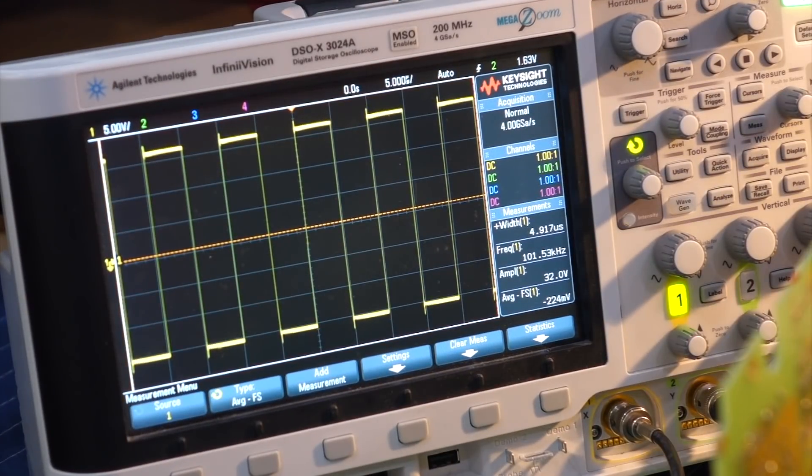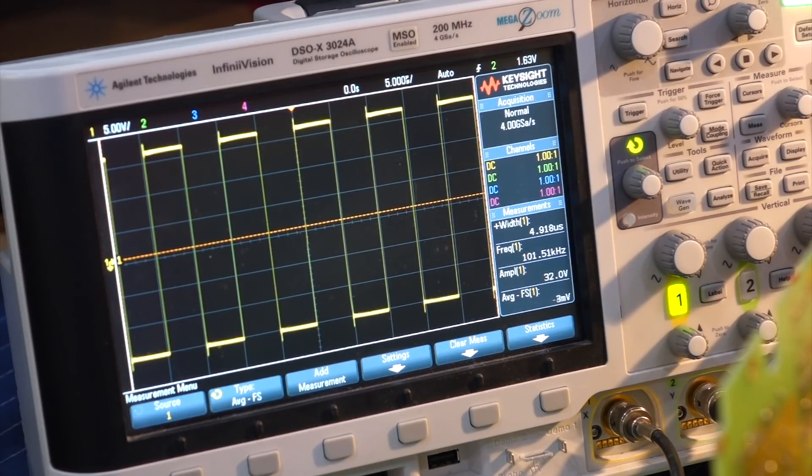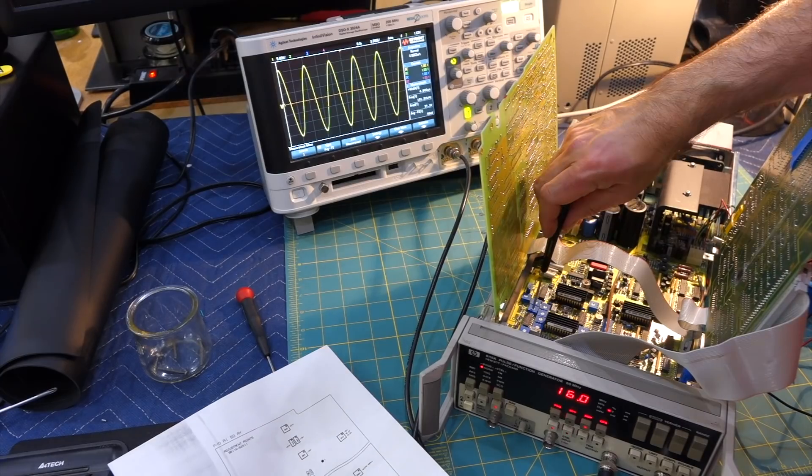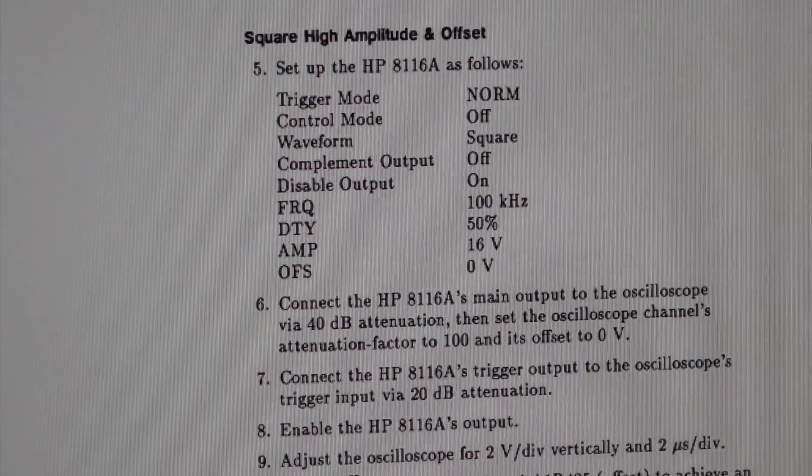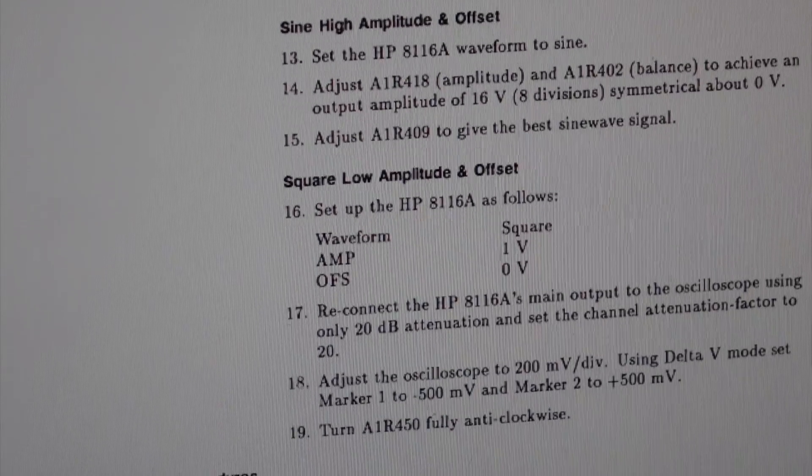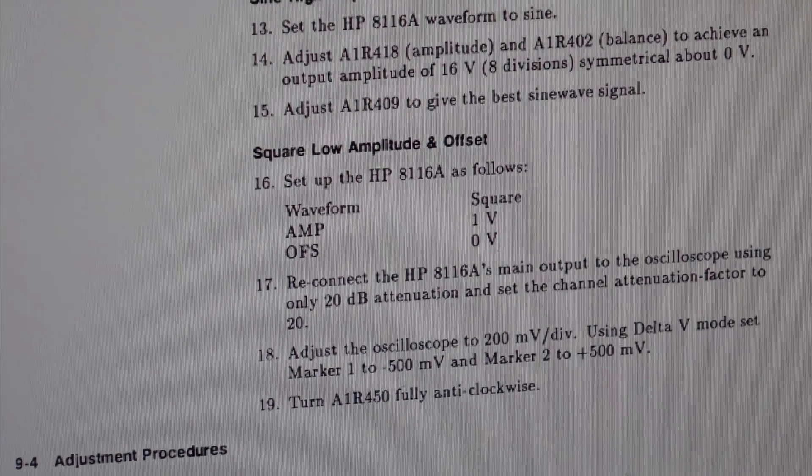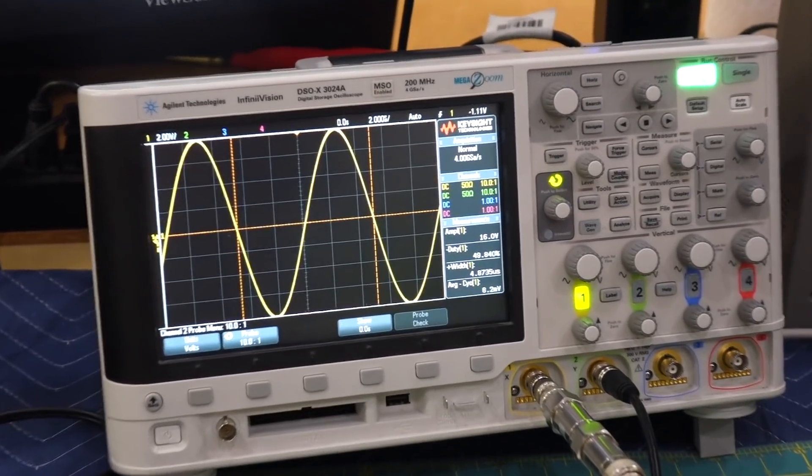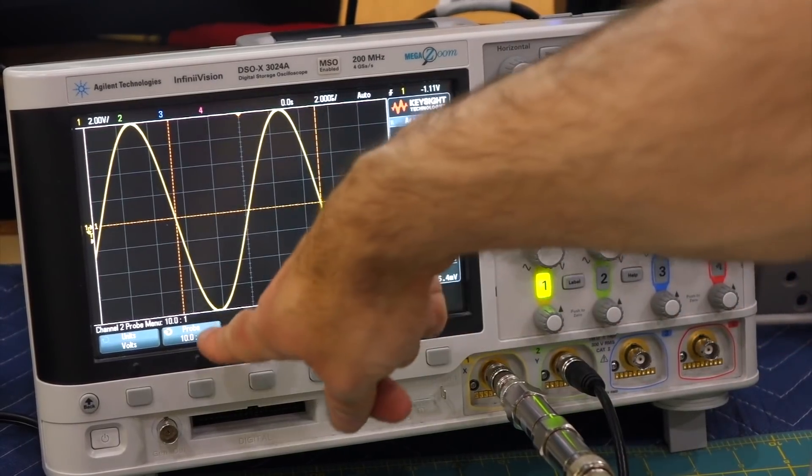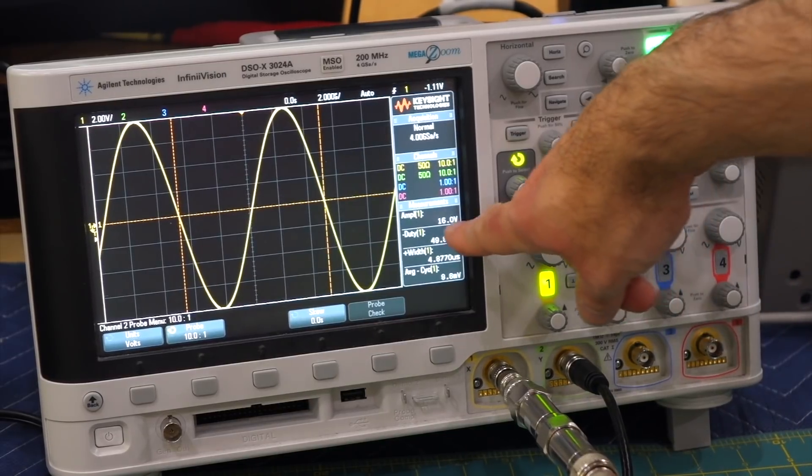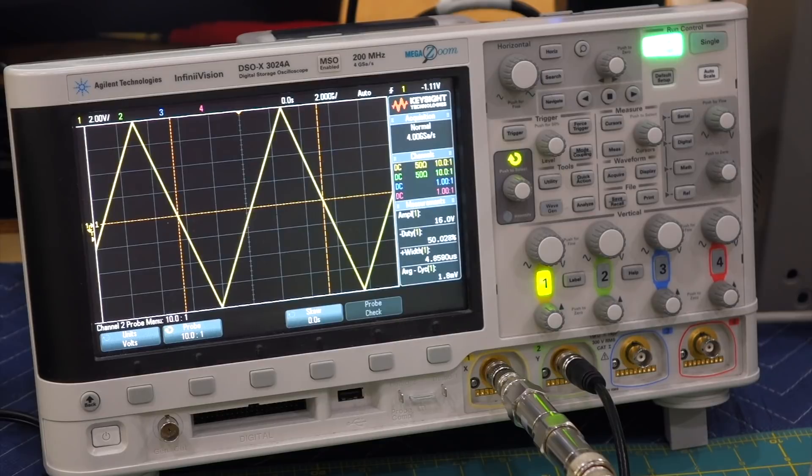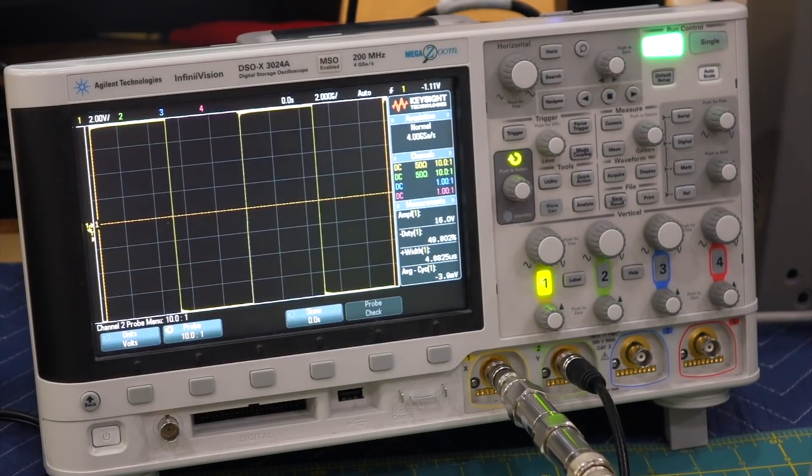Then there's a bajillion pots that you have to adjust. And you're told which one that is. There's one for every thing in this instrument. You basically have to adjust the amplitude and zero offset separately for square, triangle, and sinusoid waveforms. An annoying total of six pots. This is all done by watching the scope. So your scope better be calibrated to start with. Oh no, after you've done it all for high amplitude, you need to repeat for low amplitude. My goodness. So now we're good. We are in 50 ohms with 20 dB attenuation. I've put a ratio of 10 to 1, because 20 dB is 10 attenuation. And I have 16 volts in sine, in triangle, and in square wave. Phew! You got it.